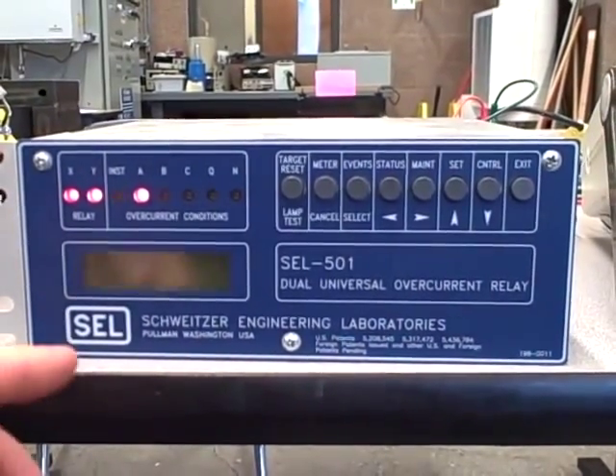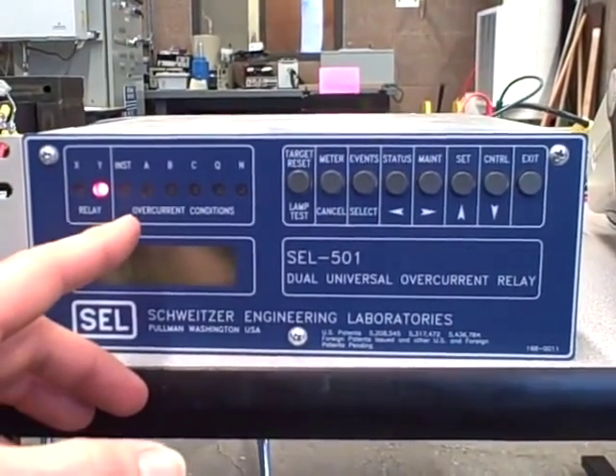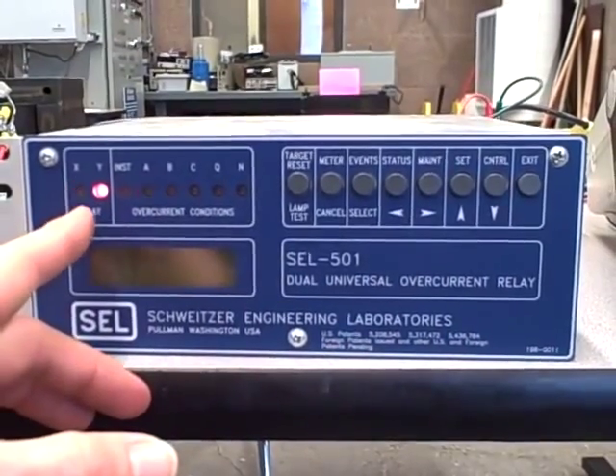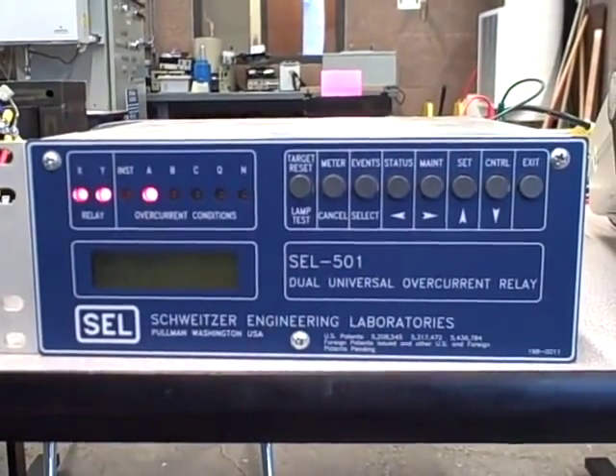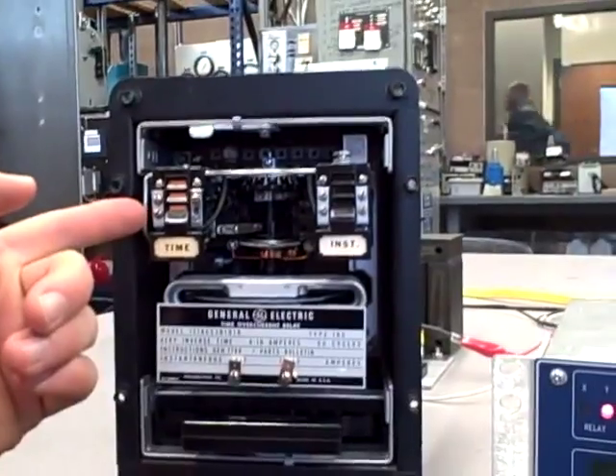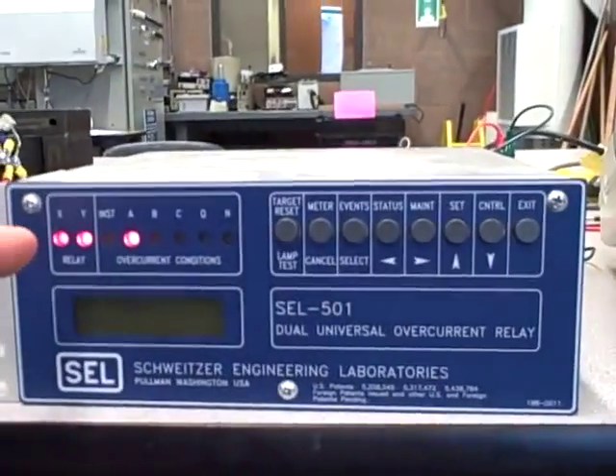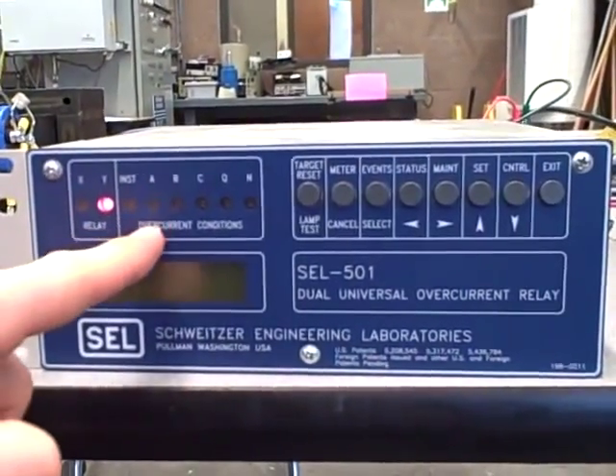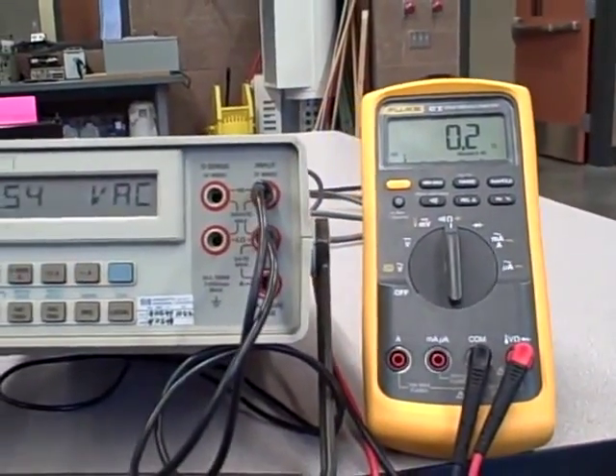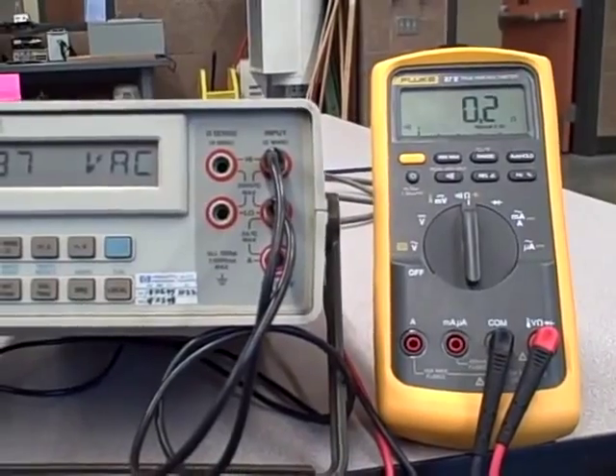There we go. So right here, I have an overcurrent condition. It's flashing the targets at me, so it's similar to having this go orange on the old technology. I just have flashing lights telling me which relay tripped and which phase it was. Of course, our Fluke meter over here is beeping at us, which tells us that contact is closed. It's trying to trip the breaker.